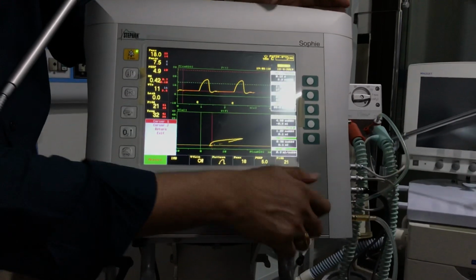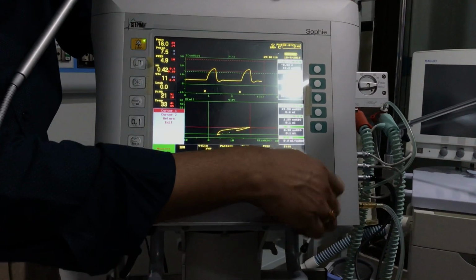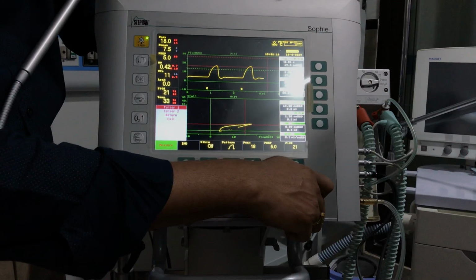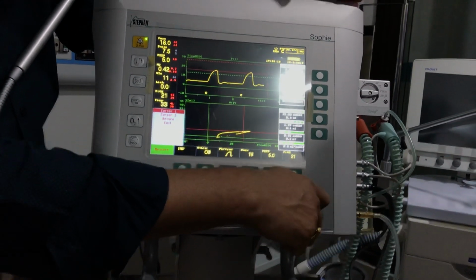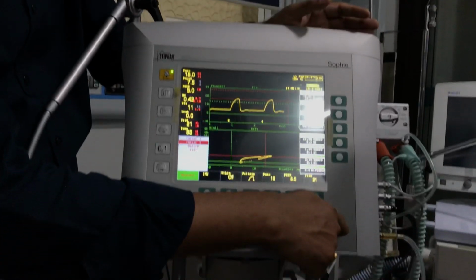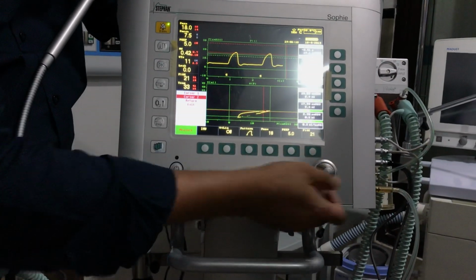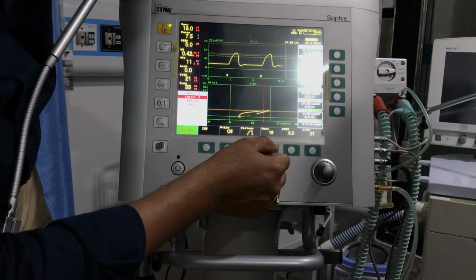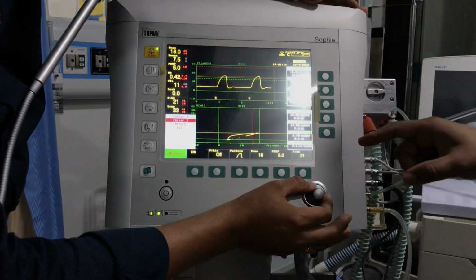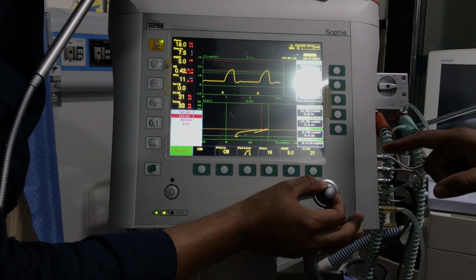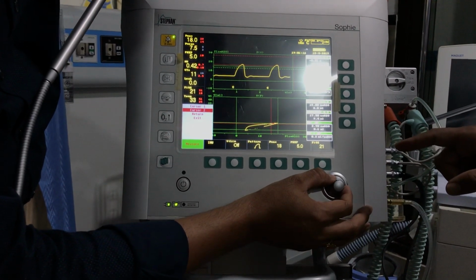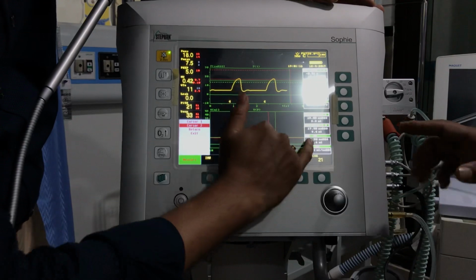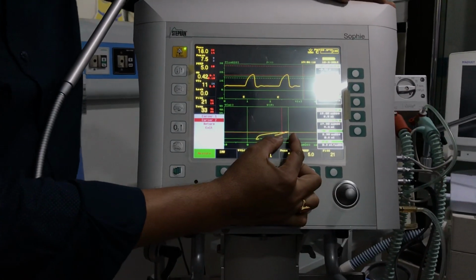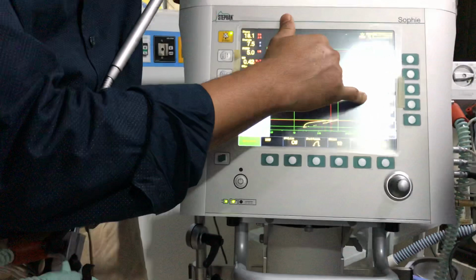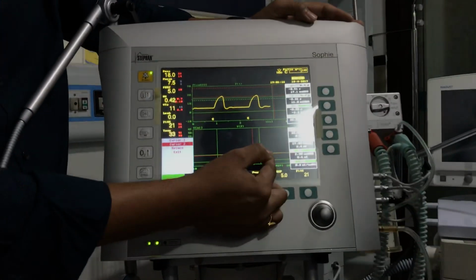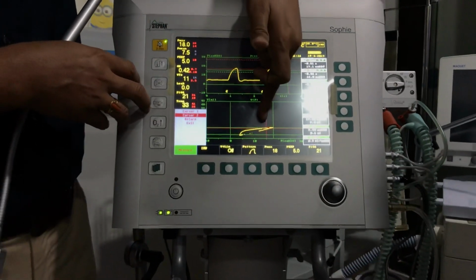So I'll have a cursor here, one cursor, maybe somewhere here, and then I'll take the second cursor. Now the difference between these two is roughly around how much it is. I can see this digitally. This pressure is from 17 to 15, 2 centimeter water. Yeah, 2.9. So actually you should block this at 15 because the inflection started from that only. So I will limit it to 15. I will decrease the PIP then.